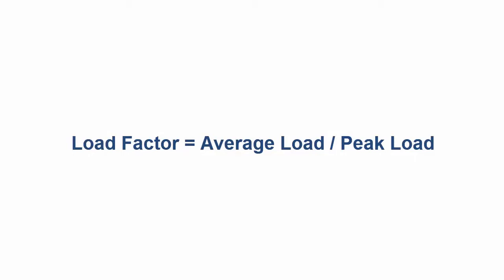The load factor is the ratio of average load divided by peak load. It is desirable to have the load factor as high as possible, meaning the peak load should be very close to the average load, so that peak power is not much higher than average power. For example, if your average power is 300 kilowatts and your peak power is 600 kilowatts, there is a 300 kilowatt difference.